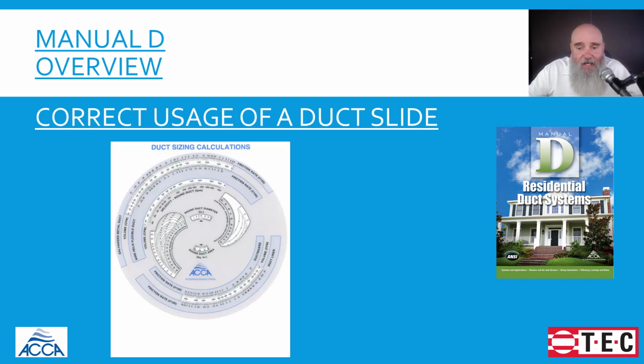What we want to do is calculate our friction rate following the guidance in ACCA's Manual D, and then we get to use the duct slide. Often referred to as a ductulator, it is a piece of, I'm going to call it technology, which I guess it is, but it's really nothing more than a slide rule, and it allows us to determine what size ducts we need to get the volume of air that we need to go to a space, again, at that acceptable velocity.